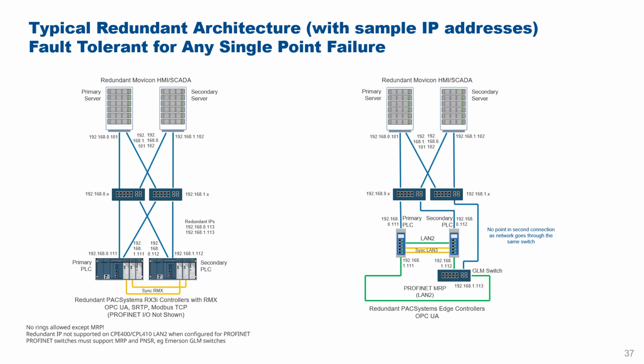So this would give you the benefit of separate Ethernet ports and being able to communicate directly using these multiple IP addresses. So you can see here that because we've got all these different IP addresses, the networking configuration can get quite complex, but effectively at the higher level, you've really got 2 networks. So you've got your master network on 192.168.0, you've got your backup network on 192.168.1, and then you assign your IP addresses accordingly. Now on the IO side, the IO network would be a separate network, because with the CPE330, you've got the option of using either the separate Ethernet module in ETM001 or a separate Profinet controller, and the benefit of that means you can segregate all of your networks.